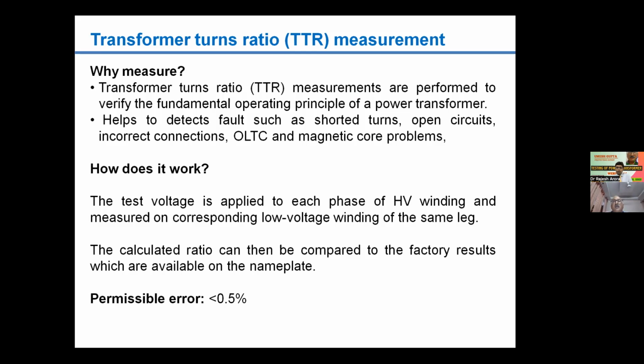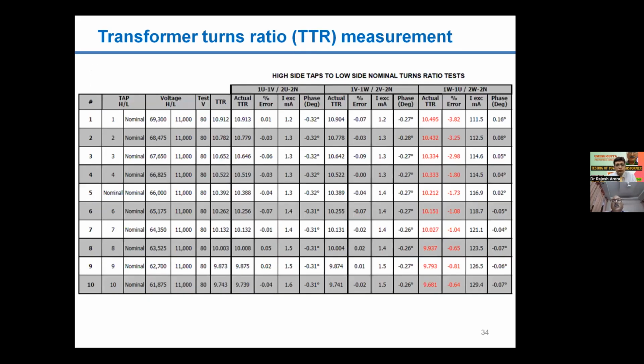How is it done? HV winding is given high voltage, and low voltage winding measurement is done and the ratio is calculated. The permissible error, as mentioned, should be less than 0.5%. Nowadays, this is done through a kit, and the kit has an arrangement to show you the complete table, complete result, including ratio as well as the phase angle error, and both errors are combined in the composite error.